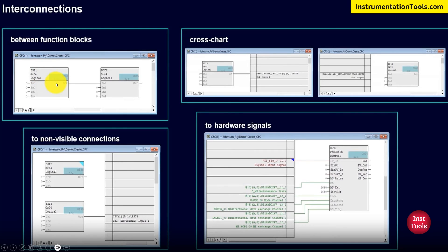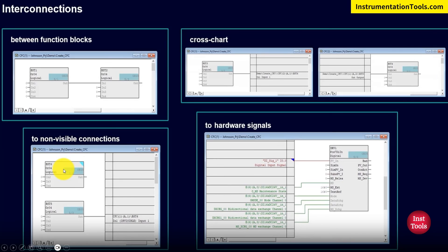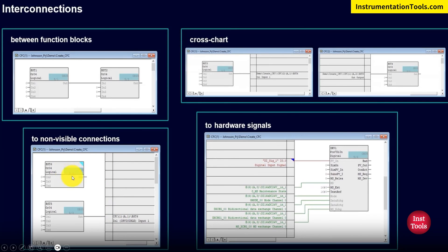Now let's look at the interconnection possibilities of function blocks. First, direct interconnection: a direct connection is accepted if both data types are the same. Second, cross-chart interconnection: if we create two different CFCs and want to interconnect them, it is possible by opening both CFCs and making an interconnection. Third, non-visible connection: FB blocks have many pins that may not be shown — internally they might be configured. These can be enabled through the corresponding FB block's object properties under pin visibility. If a connection is made to a non-visible pin, the corresponding pin will blink in blue, indicating an invisible interconnection exists.